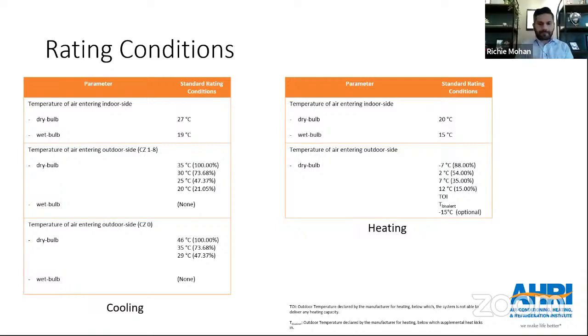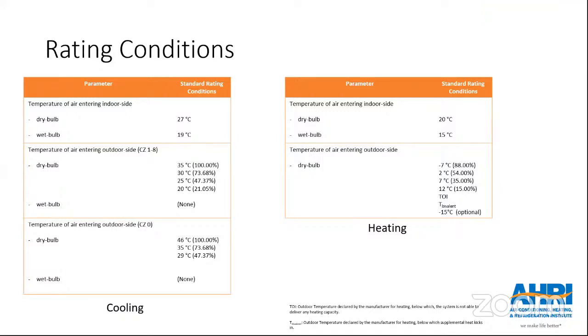So how is the Indian standard handling the relative humidity requirement at this moment? In the Indian standard, the ISEER value is load-based. We calculated load bins instead of temperature bins. The temperature bin approach, which was initially used in many standards, kind of neglects the effect of humidity. In the Indian standard, we calculated load bins using simulation of actual buildings, and then determined the weightages of A, B, and C, and the outdoor conditions corresponding to A, B, and C. So it was based on simulation, with those conditions kept instead of only the dry bulb based linear value.